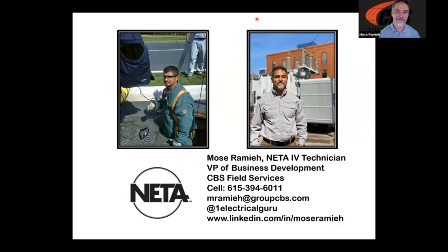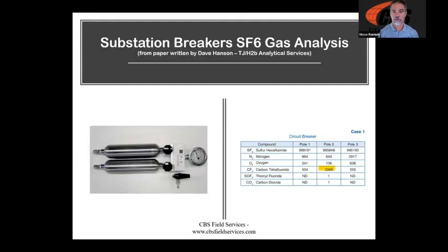Yes, sir. When this test is done, is the gas being tested purged into the environment? So there are some test sets that basically take a sample and do purge it to the atmosphere. That is one of the advantages of the bottle, and let's see how quickly Mose can find that for us, is that it does not purge it to the environment, right?